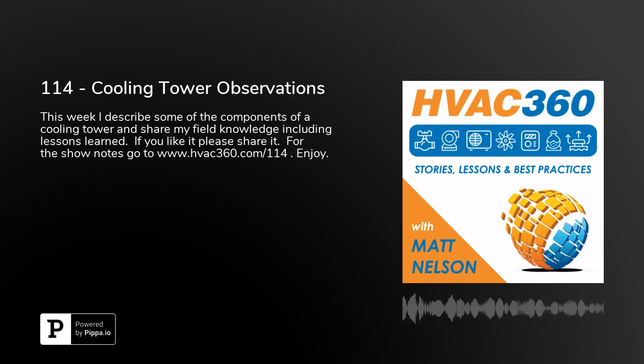Things to think about: variable flow. I know there are a lot of energy savings that go along with pumps and fans. You've got a VFD on the fan. You can also do variable flow on the pumping system to save pump energy, which is pretty big. But you have to watch out for partial fill coverage. If you have some isolation valves that don't work properly, or maybe you don't have any at all, you could run into a scenario with multiple cooling towers where the water goes up to the fill and doesn't spread out like it should. So you're going to be derating the fill, or derating the capacity of the tower, just by not flowing enough water through it. Just like many devices, there should be a minimum flow over a tower to make sure that you get the desired result that you want.